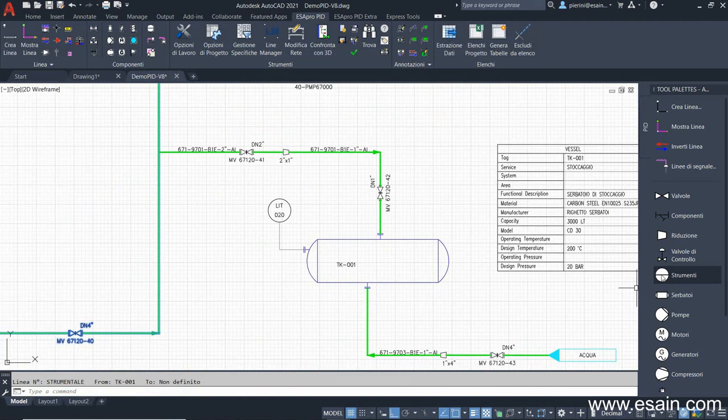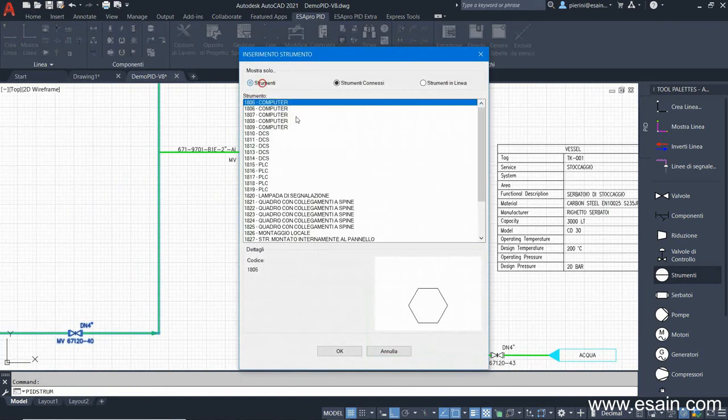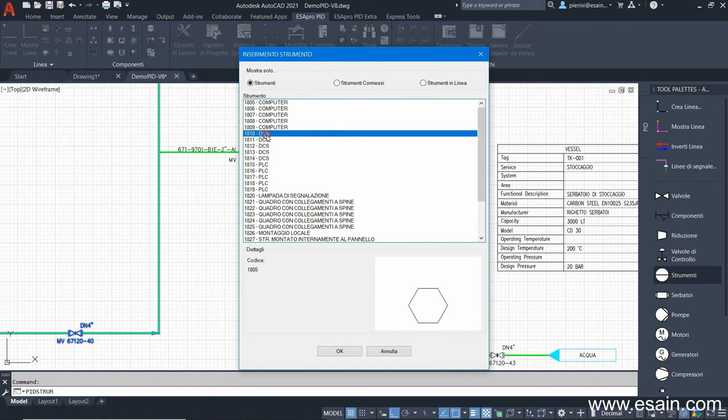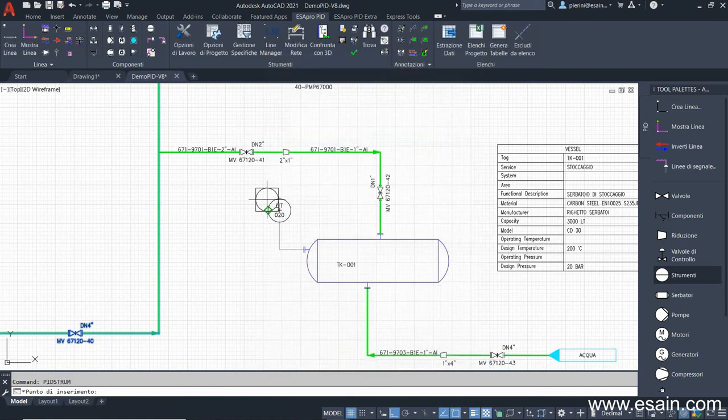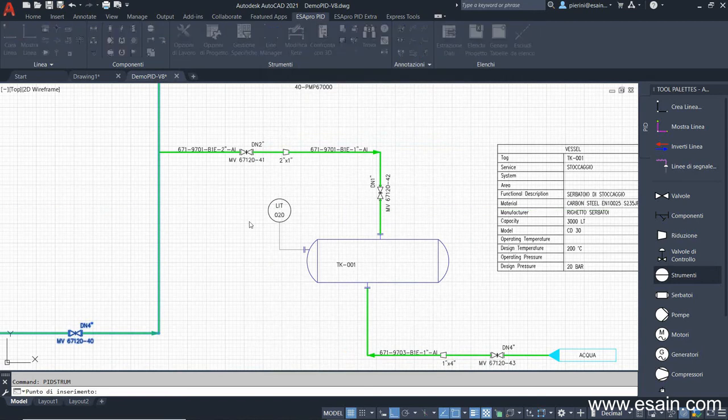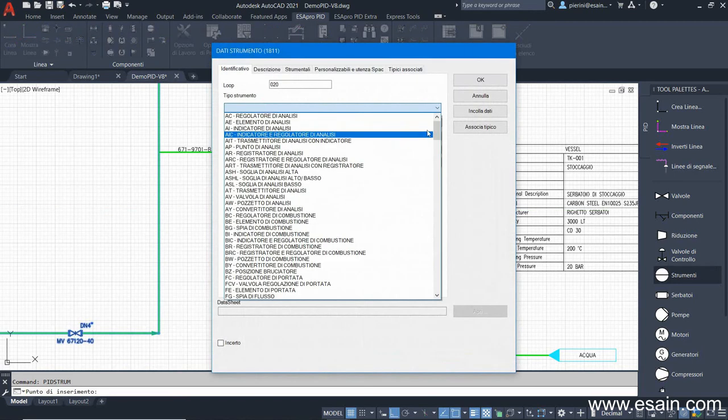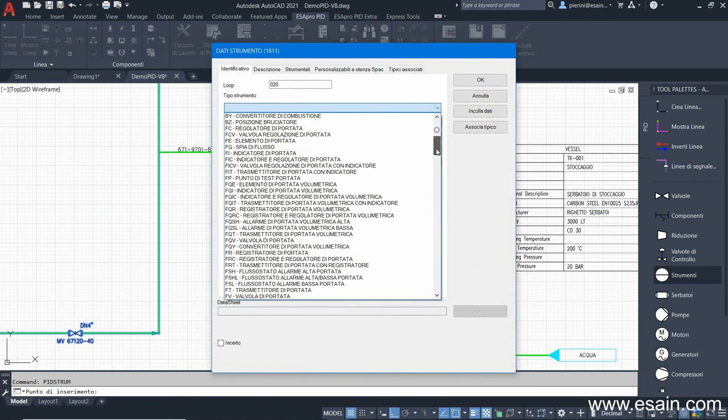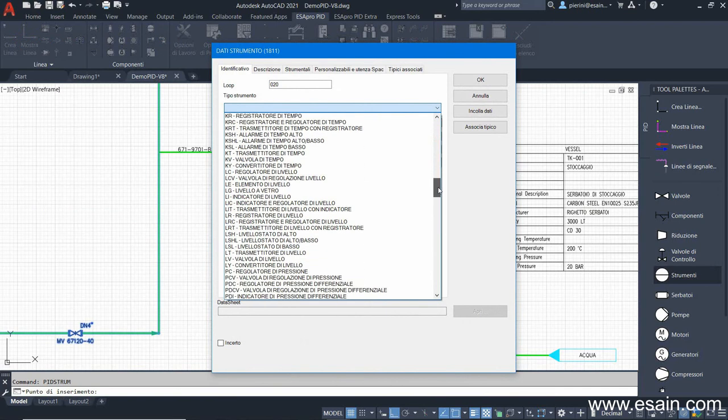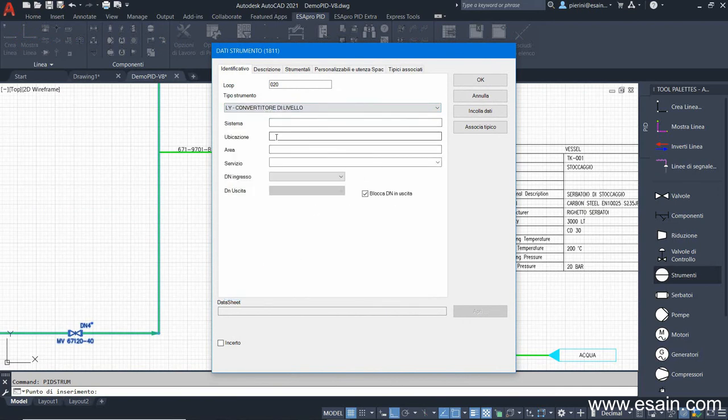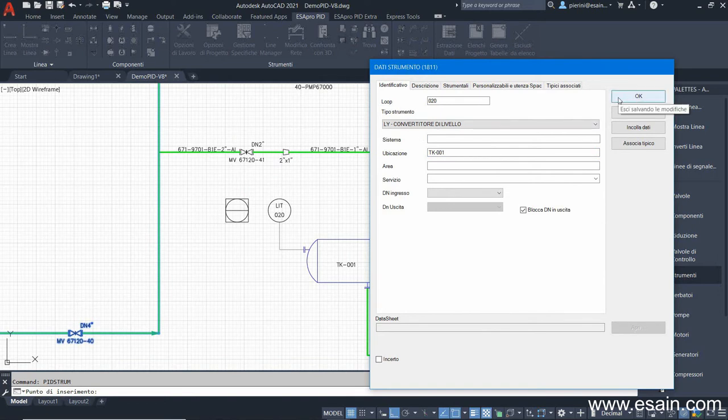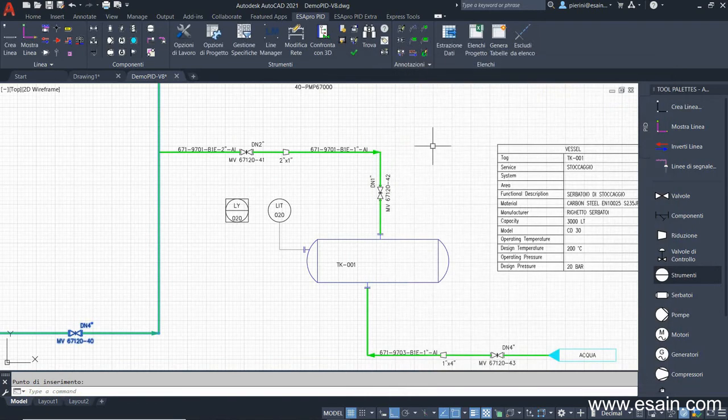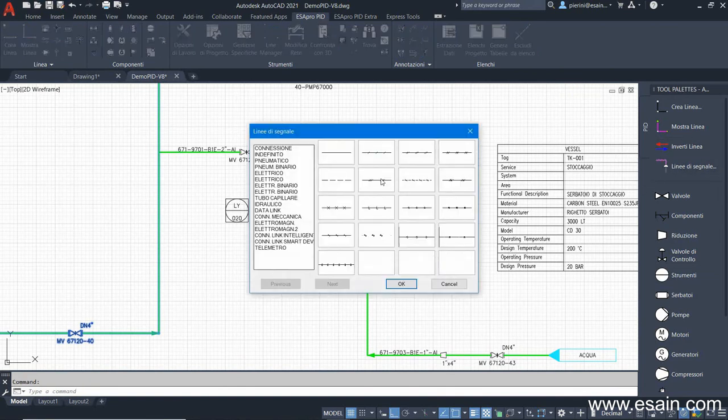I proceed with my loop by inserting a discrete instrument, a DCS in this case, which will receive the electrical signal of 4 to 20 milliamps from LIT. It shares the same loop and therefore has the same number. But the function in this case is converting, so it is a level converter. And being discrete, its location must be specified manually by the user. It's located on TK001. We now connect the two instruments with an electrical signal line.